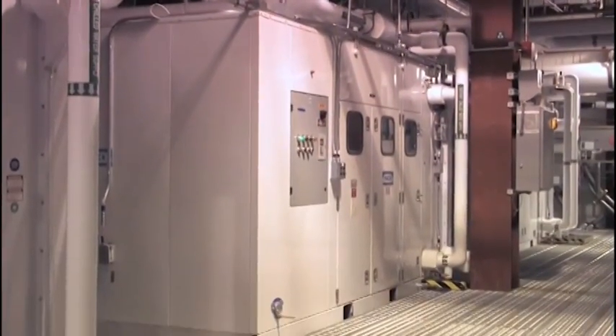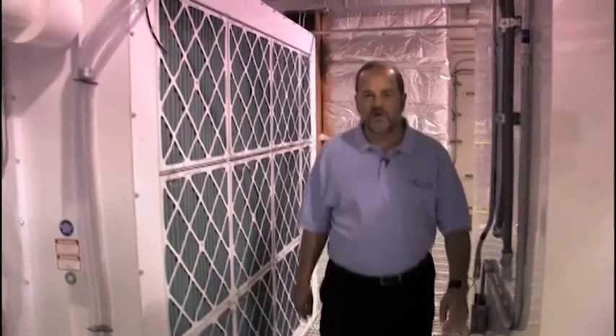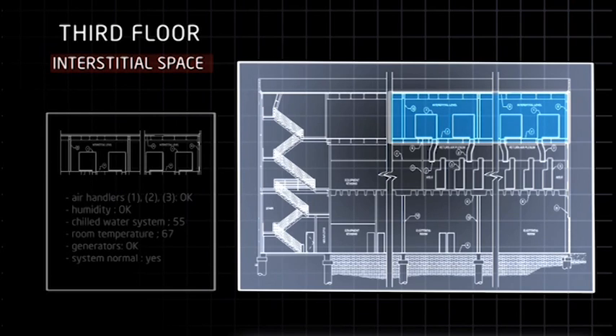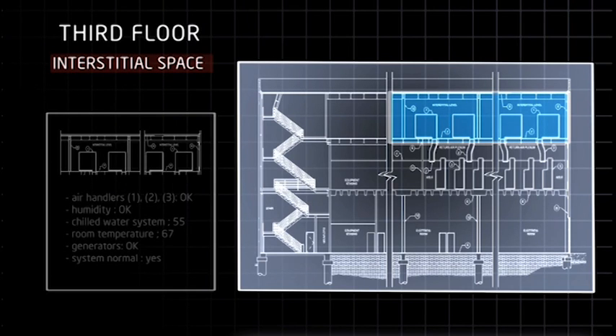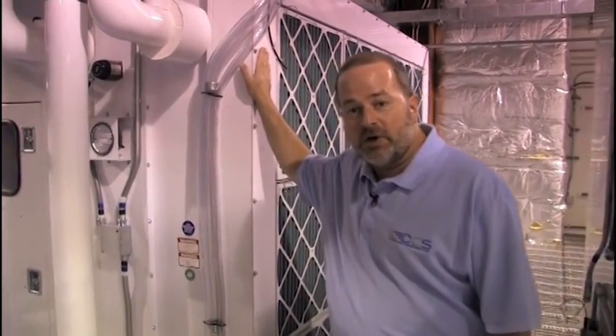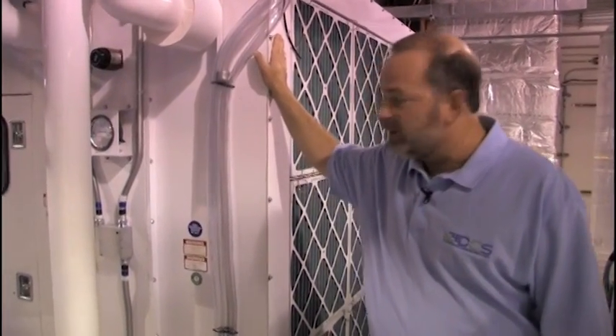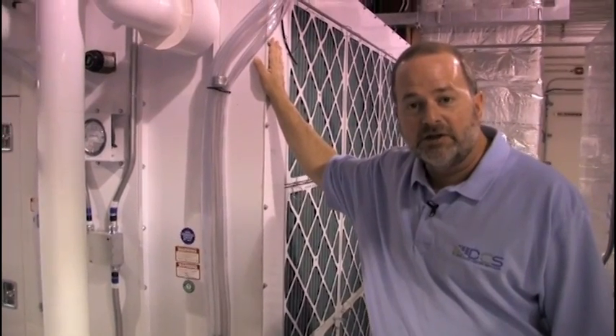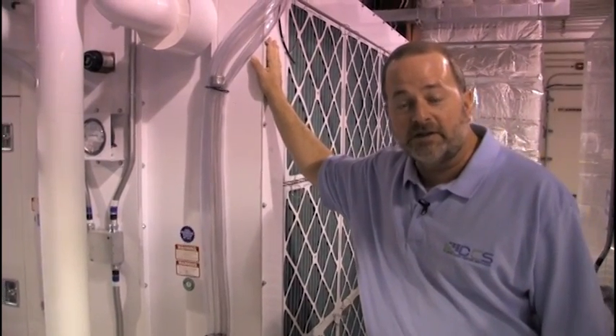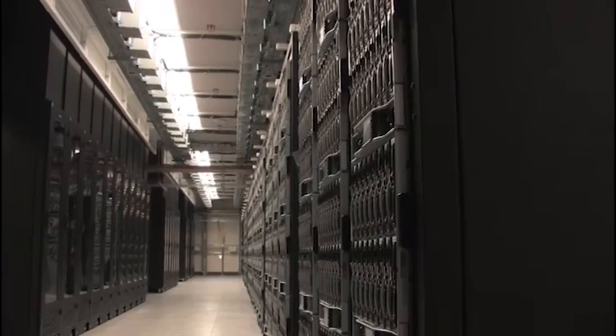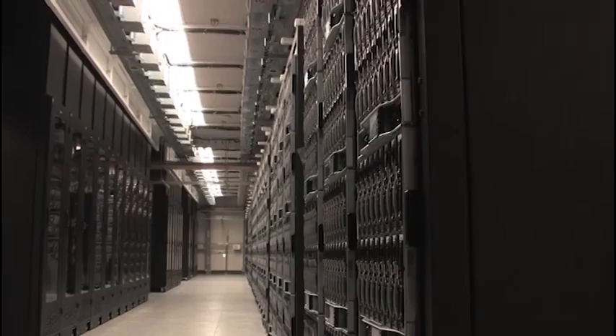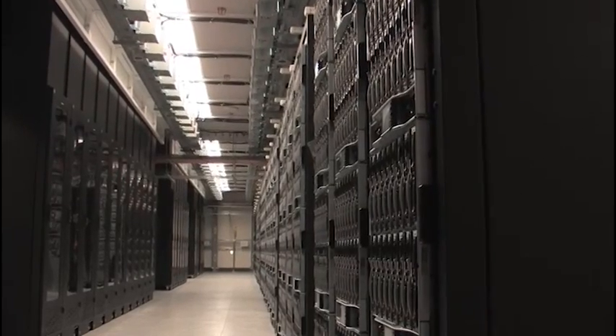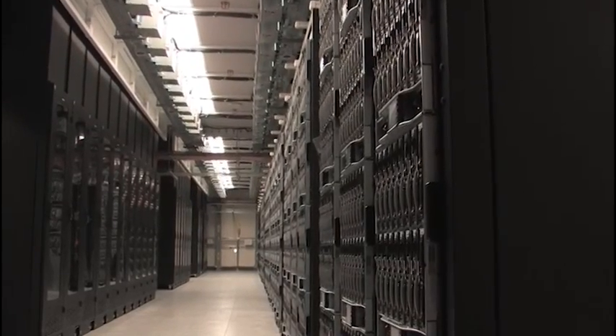We're on the third floor of the factory building that we retrofit for our computer room. This is also called the interstitial space, where we have all the air handling units. As you can see, we added capacity by putting another chilled water coil on the back of these existing air handling units to meet our capacity needs for cooling. We also gained valuable floor space in the computer room by not having to put computer room air conditioning. So we used the factory to our advantage.